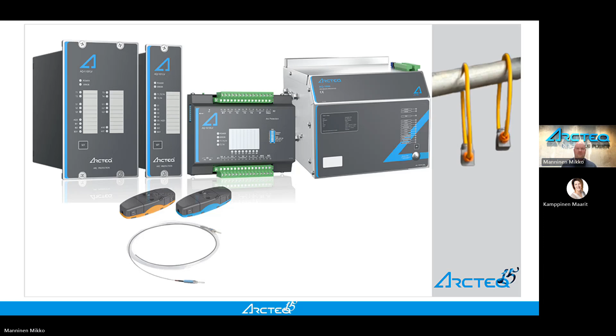First, I will introduce the Rogowski coil support as an alternative method for measuring, monitoring, and detecting high currents during the arc flash. Conventional CTs, conventional current transformers, don't disappear anywhere. They are still always available here and with the products, but this is an alternative method. And I will explain it a bit further as we carry on.